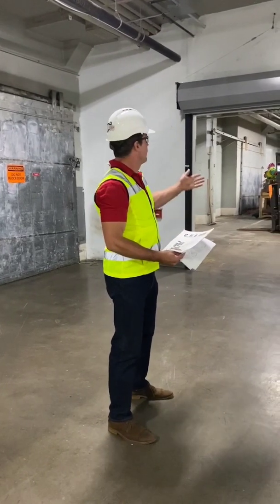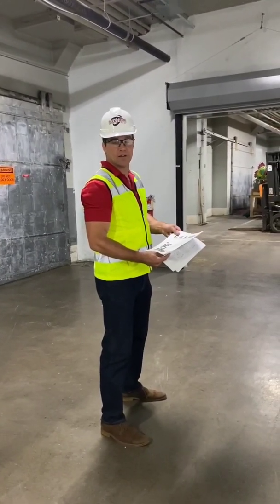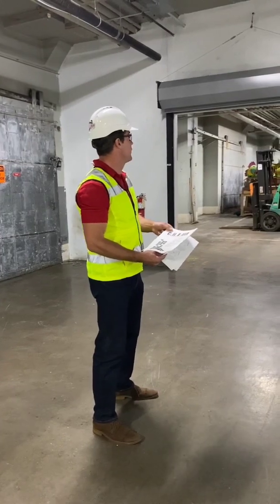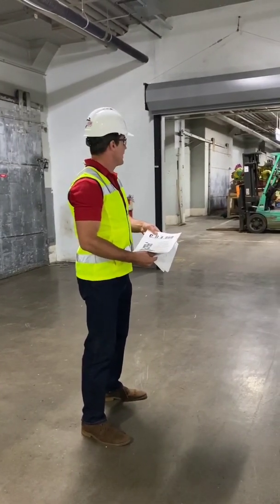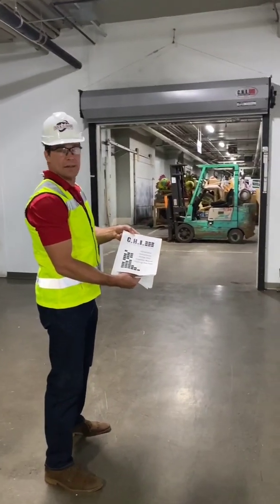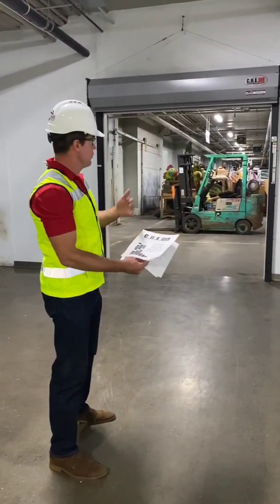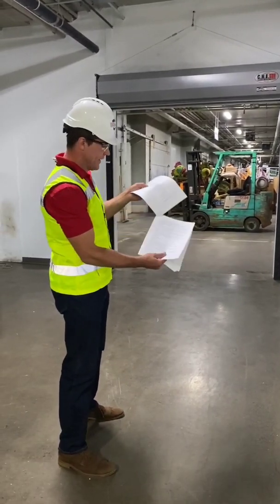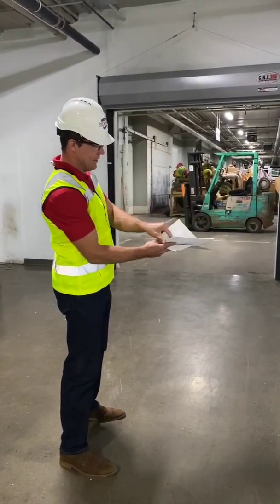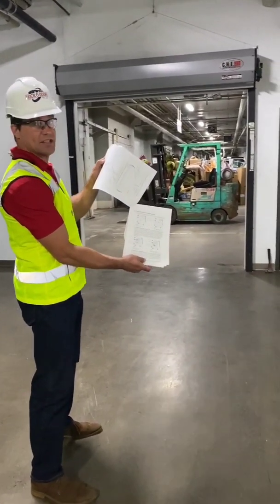Jay Anderson with Dock Indoor Tech reviewing how people certify drop tests in fire doors. One of the key things with any fire door drop test is it's critical to have the installation manual as well as the drop test information. You're going to especially need to understand the manufacturer requirements on that. As you can see, they have a very thick and detailed installation guide and they have a lot of drop test information as well.